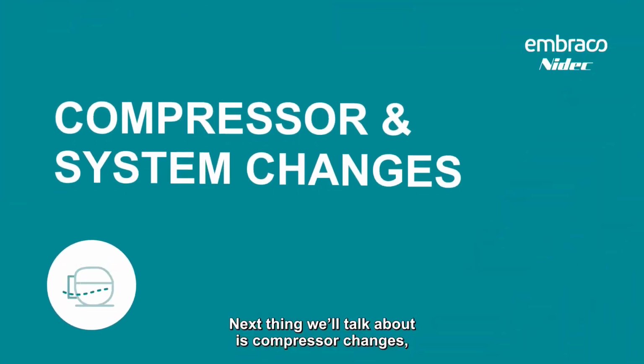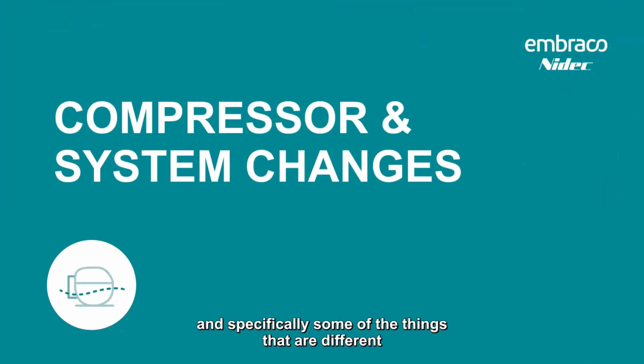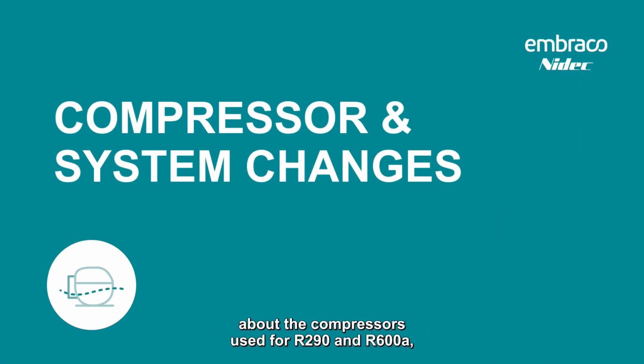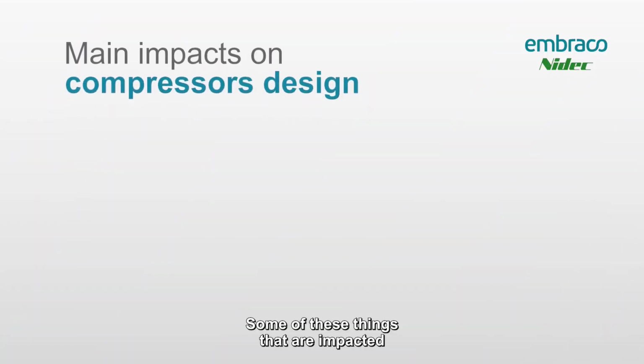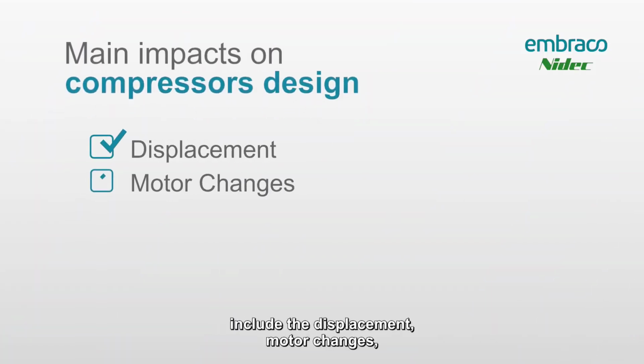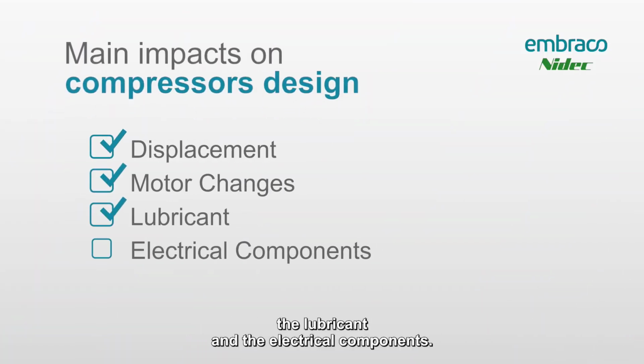The next thing we'll talk about is compressor changes, and specifically some of the things that are different and the things that are similar about the compressors used for R290 and R600a, and then also with the systems. Some of these things that are impacted include the displacement, motor changes, the lubricant, and the electrical components.